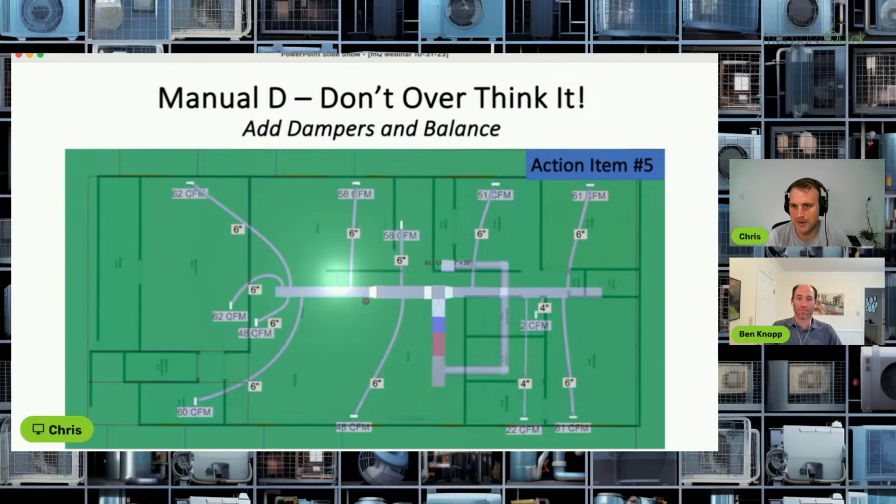I've seen designs where people will get pretty particular, where they have a 6 and a 5 and maybe a 5 over here and a 4, and they let the program drive them bananas, I guess, to try to optimize as perfect as they can. So I went into the program that did that initially, and I overwrote that part of the program, and I turned all those fives to sixes because I don't care if my ductwork's a little bit bigger.